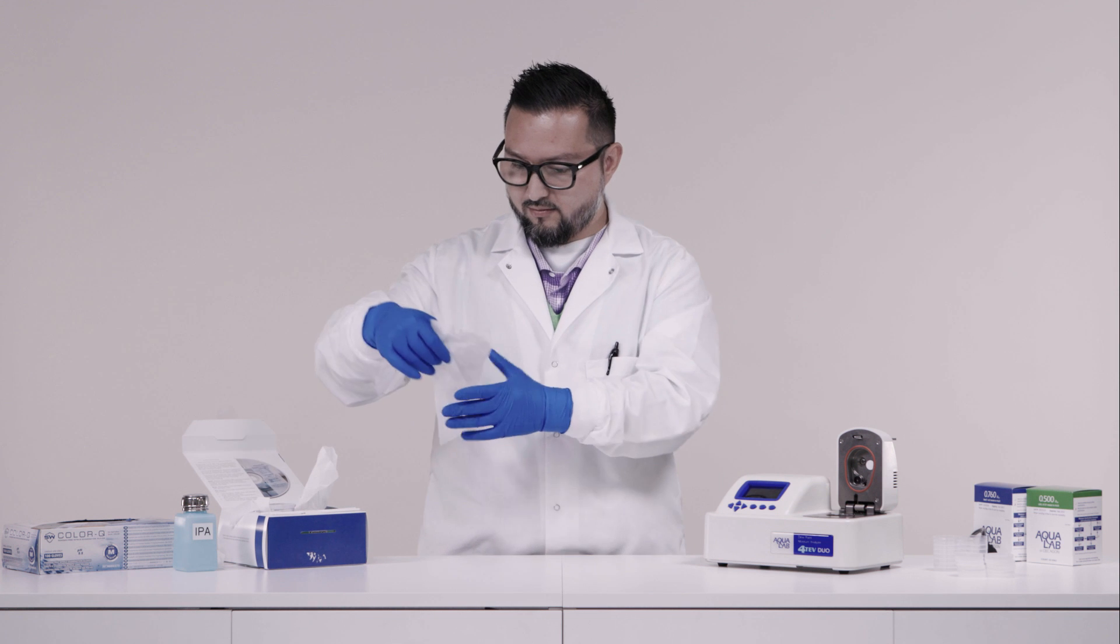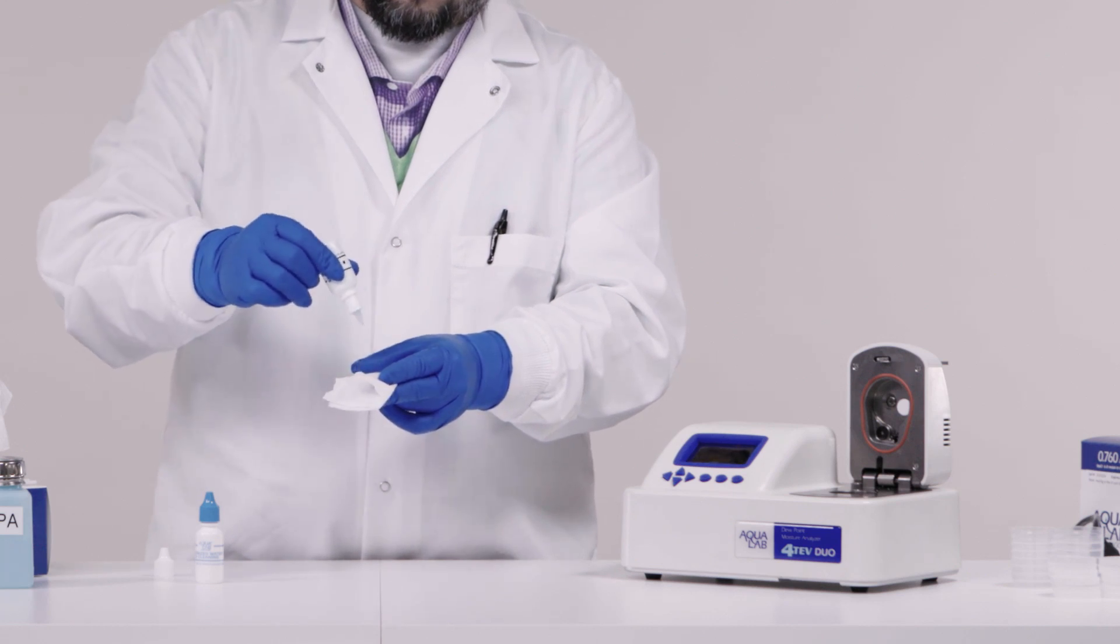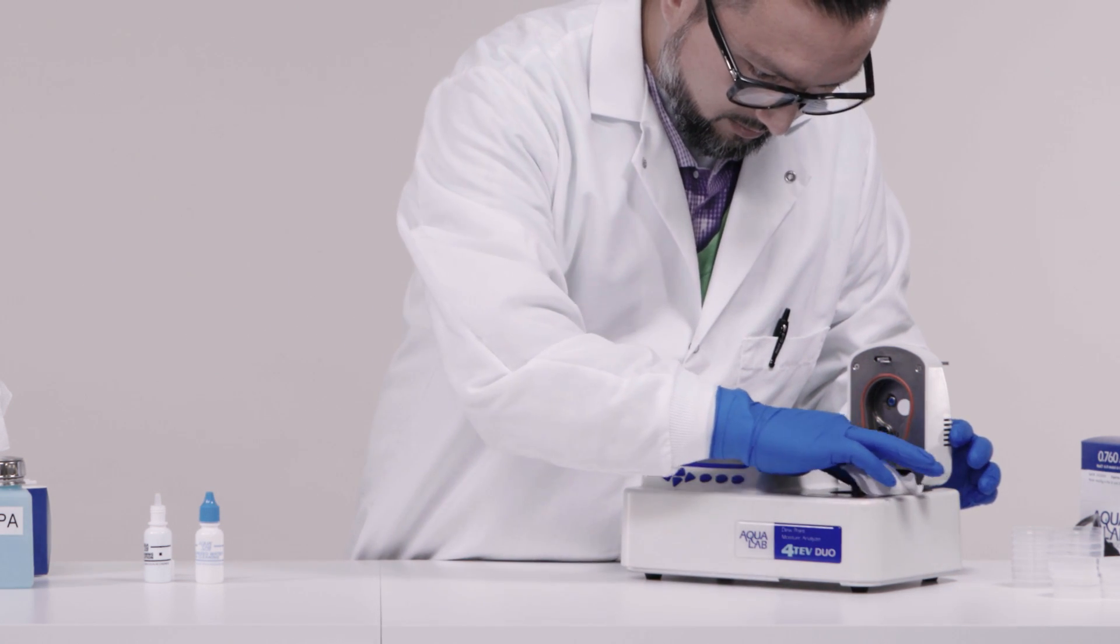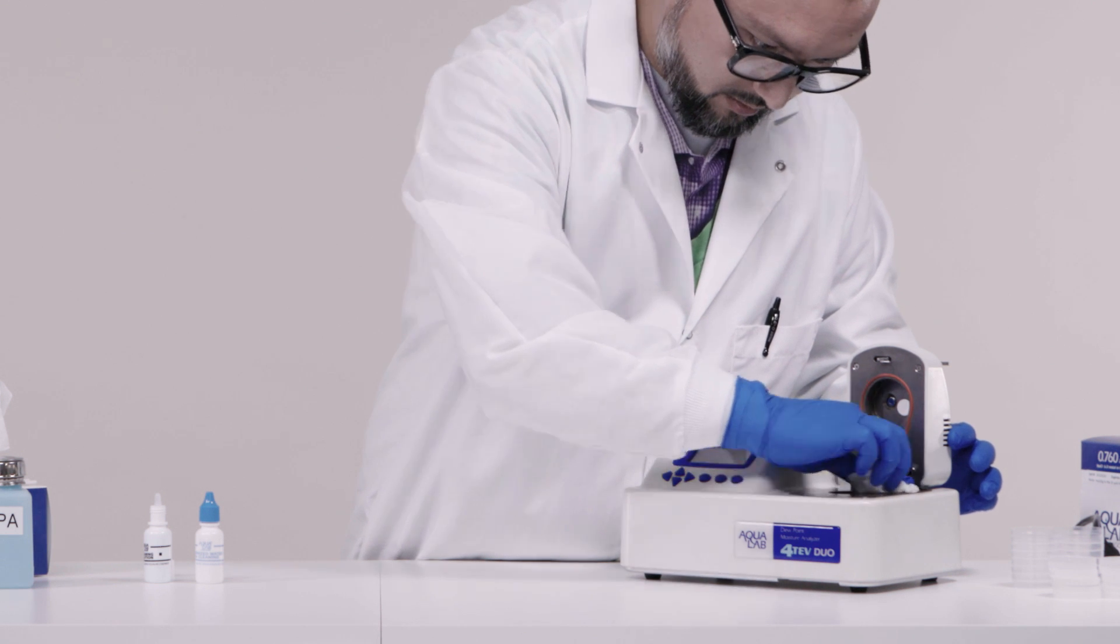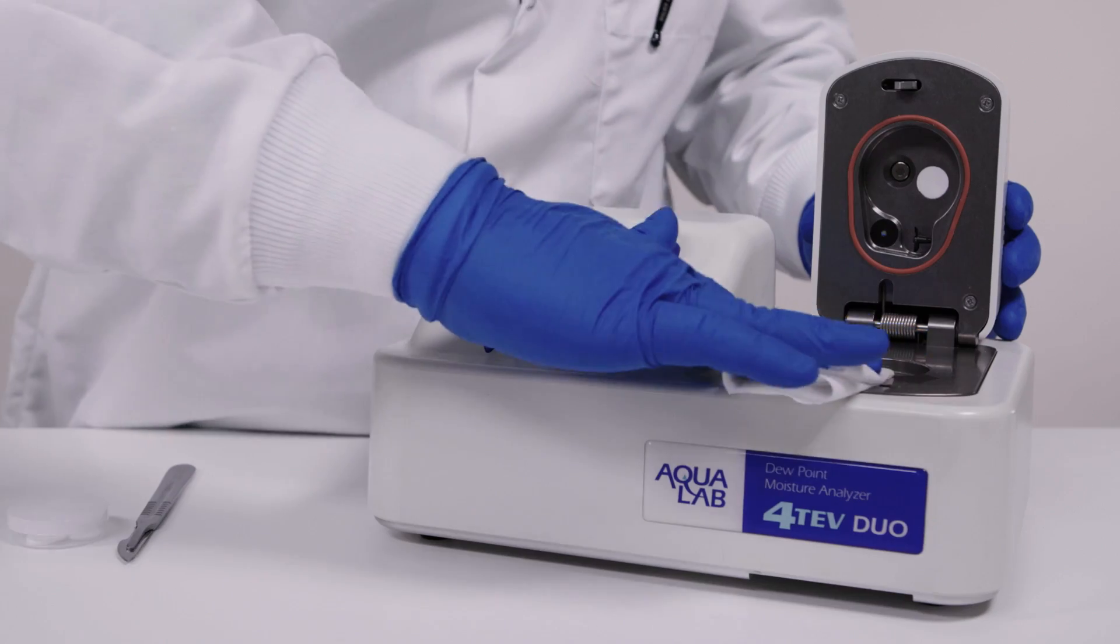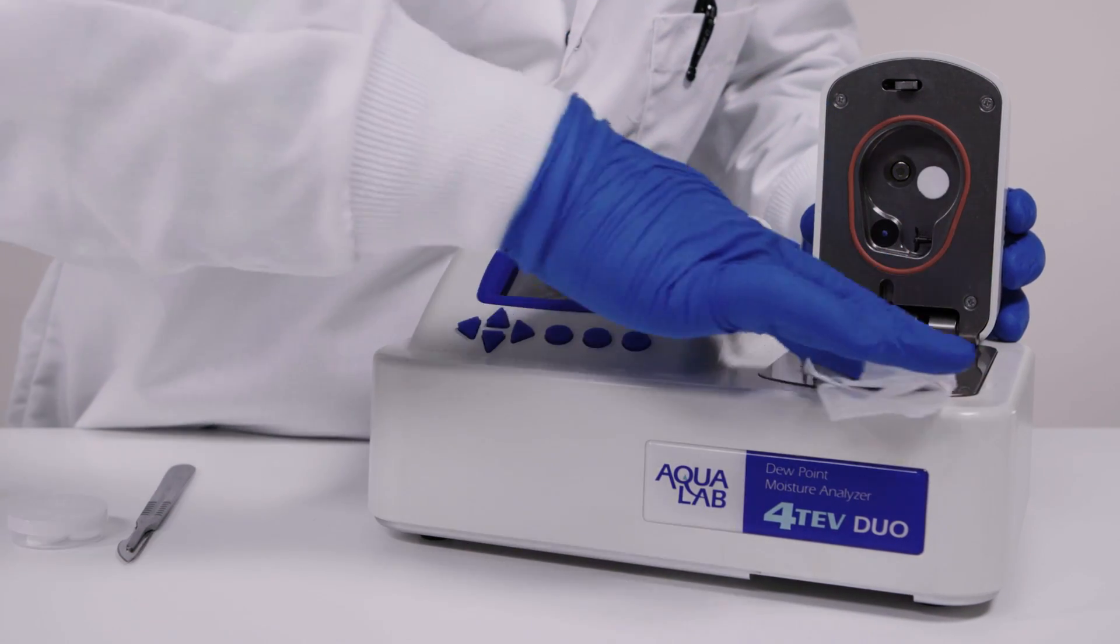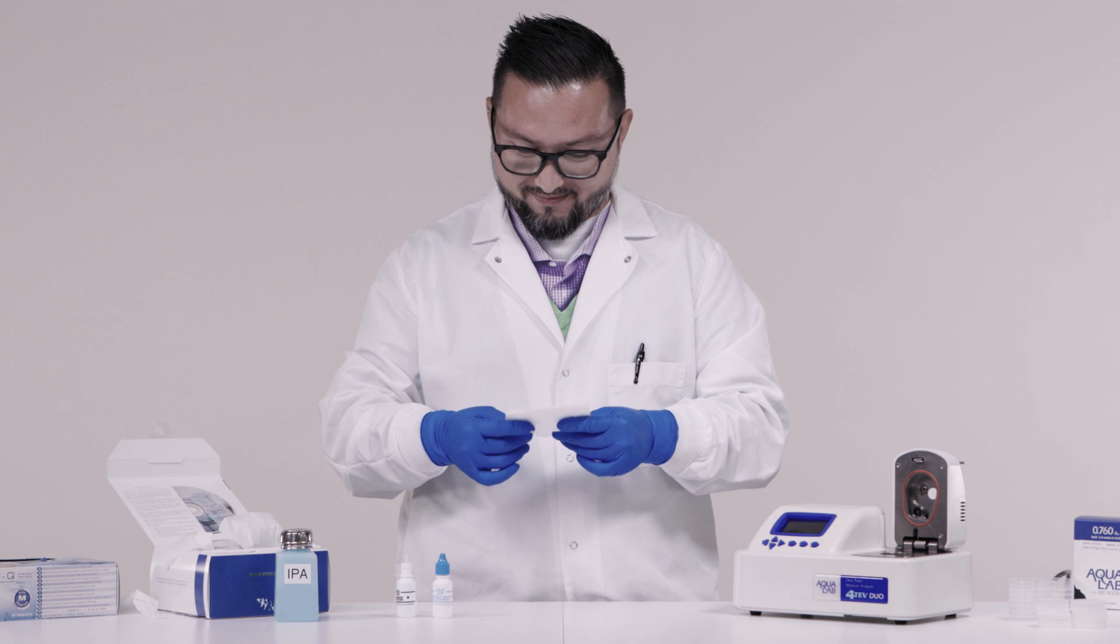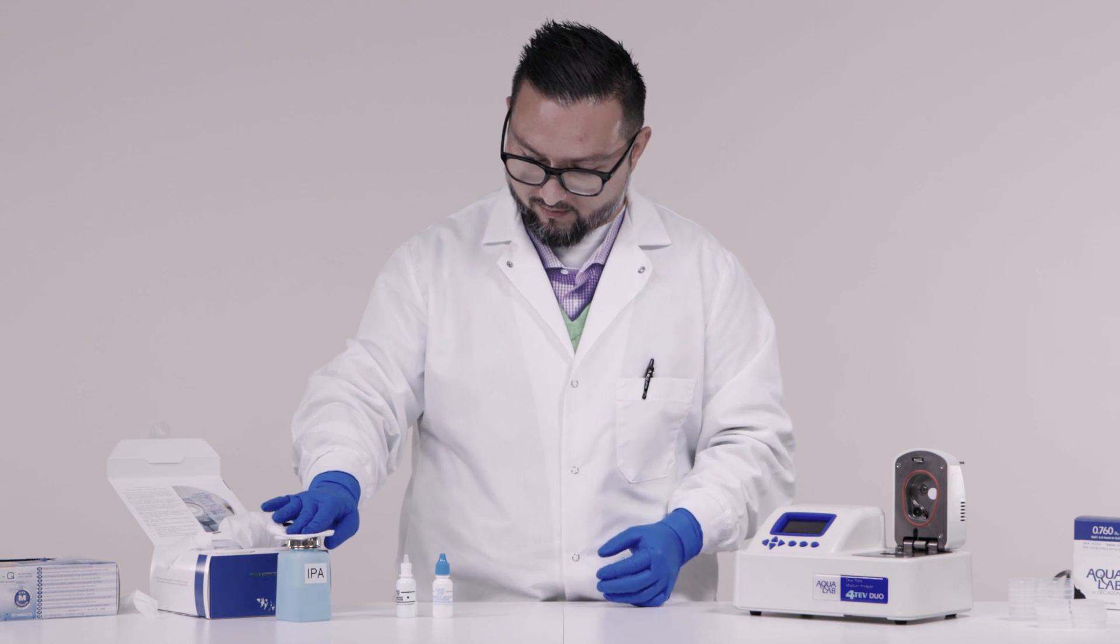Start the cleaning process by moistening a large kimwipe with isopropyl alcohol or Aqualab cleaning solution and then wiping down the surface areas of the sample chamber. Because of regulations, we don't ship isopropyl alcohol in the cleaning kits, but it's often the best cleaning agent, particularly if you're measuring samples with a high fat content. You can use any concentration of isopropyl alcohol greater than 90%. As you clean, be sure to get in the corners and around the red O-ring. Be careful not to bend the fan blades when wiping down the surface area of the sample chamber. Change kimwipes frequently, even if they appear clean. If the kimwipe appears dirty after cleaning, get a new kimwipe and repeat the cleaning process. Be careful not to dip a used kimwipe into the cleaning solution, alcohol or distilled water to avoid cross contamination.